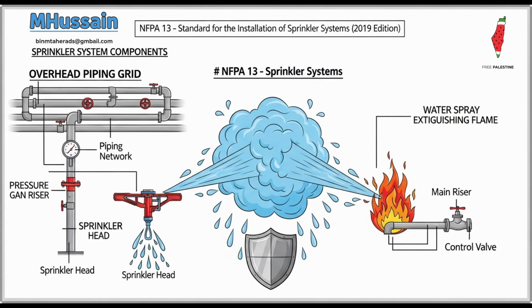Okay, let's move underground now and talk about piping installation, where protection from the cold and the earth itself is key. Right. Protecting underground piping from freezing is absolutely non-negotiable. The rule is the top of the pipe must be buried not less than 1 foot, that's 300 millimeters, below the established frost line for that specific locality. If you bury it above the frost line, you risk the water solidifying, expanding, and rupturing the pipe.